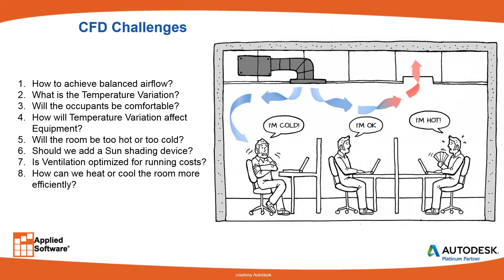You don't want to wait until the building is completed and construction is over before you test that—you want to do this as soon as possible to get the maximum impact. Some of the questions you ask yourself: how to achieve balanced airflow, what is the temperature variation, will the occupants be comfortable, how will temperature variation affect equipment, and will the room be too hot or too cold? Should we add a sun shading device to help the HVAC system from a sustainable standpoint? Is ventilation optimized for running costs, and how can we heat or cool the room more efficiently?